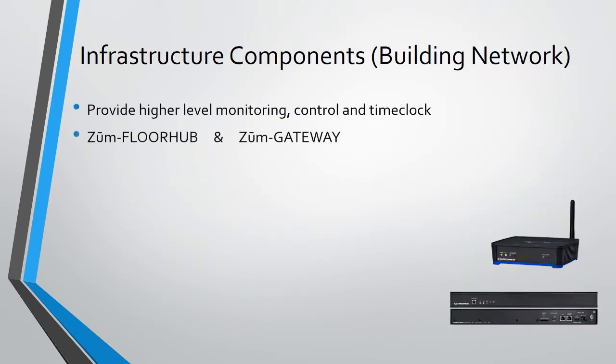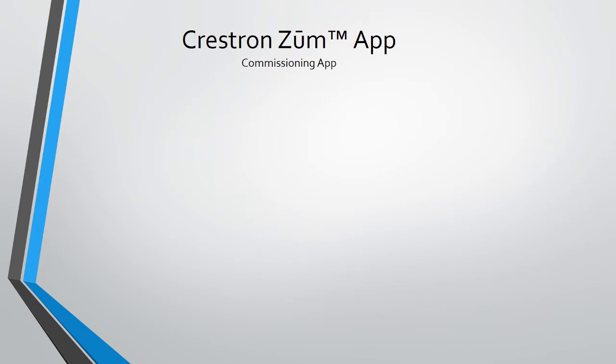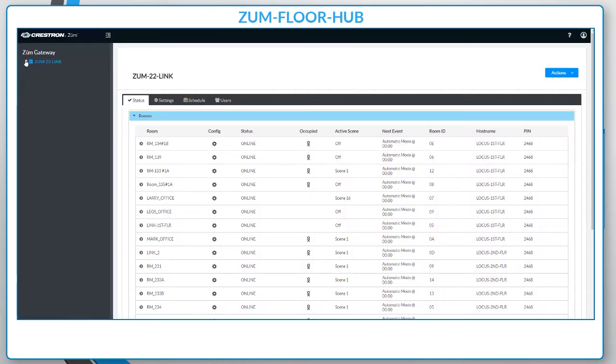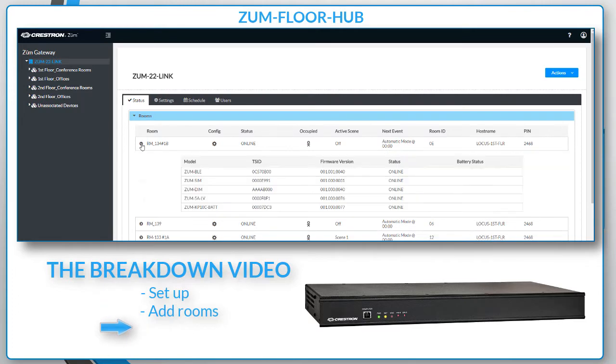Infrastructure components allow you to monitor the Zūm system building-wide. You can also remotely trigger actions like scene recall and set up automated time clock events. Keep in mind: Zūm will not communicate with Infinet EX or vice versa. The Zūm app allows easy commissioning and room configuration from your smart device — connect to the network bridge via Bluetooth and adjust scene levels and much more. The Zūm floor hub provides an at-a-glance overview of what's happening in the building, accessible via your computer's web browser. See the Zūm floor hub breakdown video for a complete explanation of setup, adding commissioned Zūm spaces, and creating time clock events.